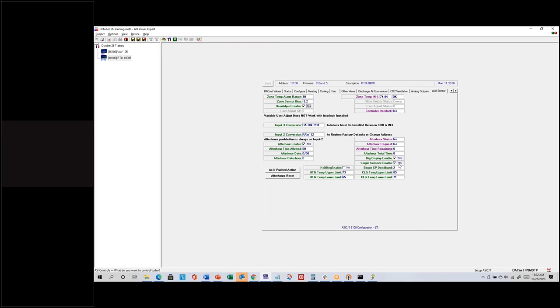We enable the digital display and single set point if we want to shift the set point together. After hours time allowed — when they push the button — can be as high as 255 minutes (4 hours 15 minutes) or as little as zero, which would do nothing. We can adjust the set points with the digital wall sensor, but it's limited by the cooling temp upper and lower limits.